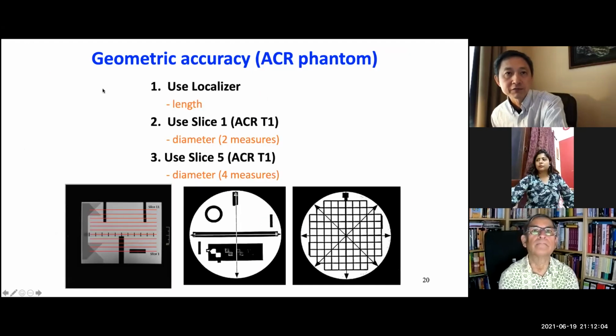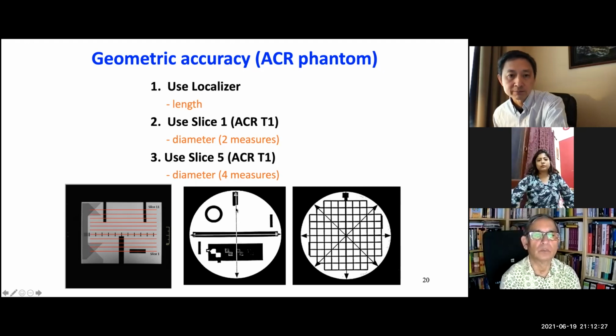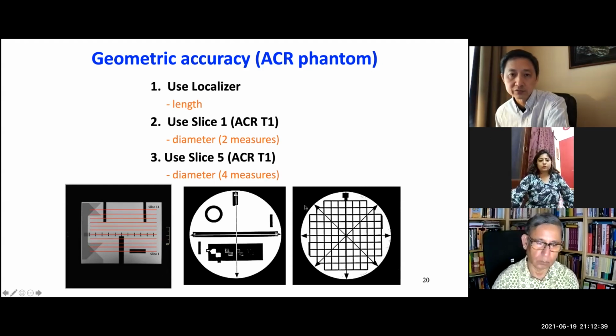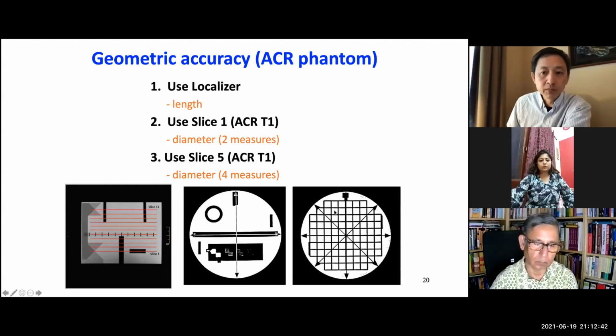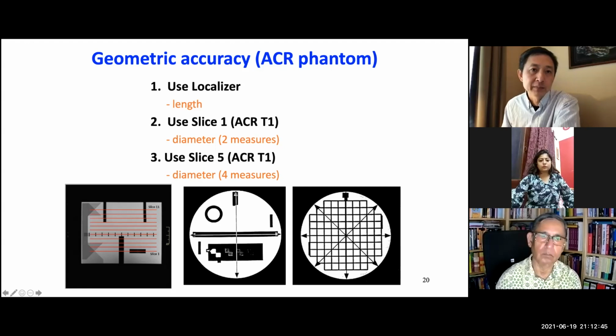When we use the ACR phantom, we measure three images. We just measure the overall diameter or the length of each image. So for the first localizer, we just measure the length. It should be 148, it's a physical length. And then we use slice 1. Slice 1 represents a little bit off isocenter, so the AP and the left-right direction. And then slice number 5. Slice number 5 is close to isocenter. We make 4 measurements, and ideally those should be 190 millimeters.